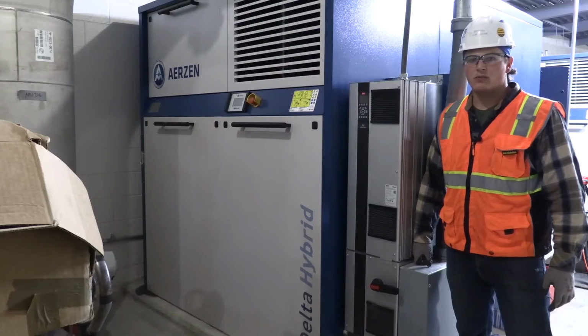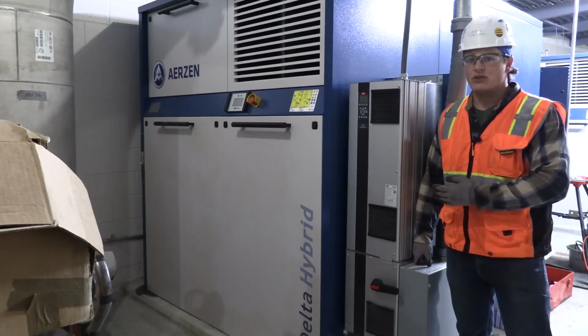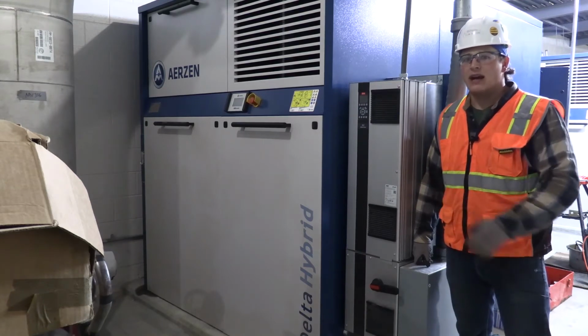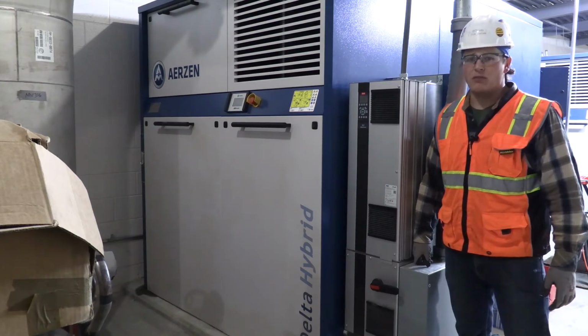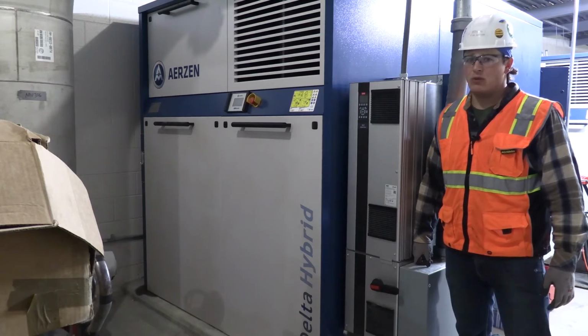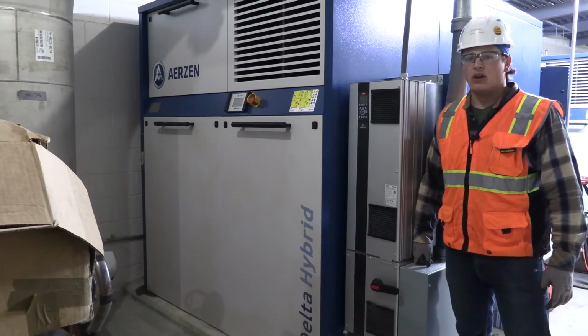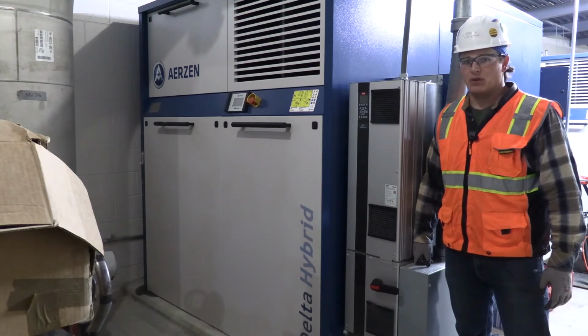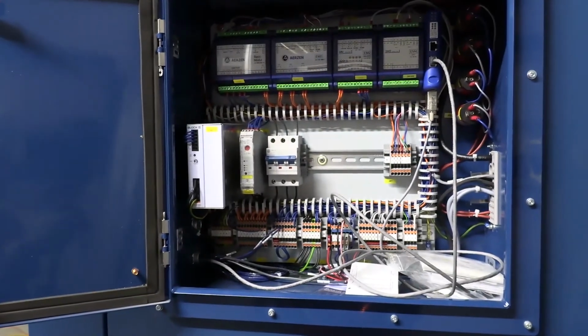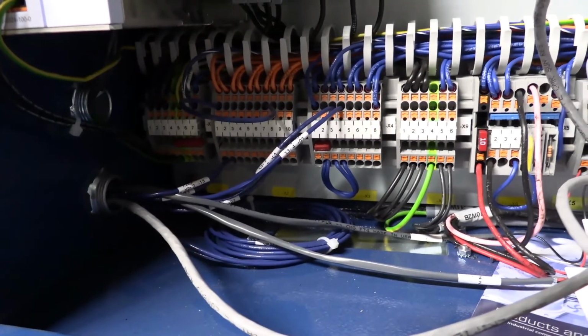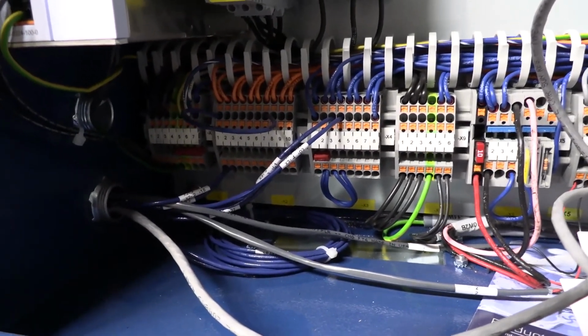When it comes to the blowers, we will need pictures of the VFD, motor starter, or controller for the blower. Not only will we need to see the control wires going back to our PLC, if they're individual wires or if it's a network cable, but we also need to see the main feed feeding the blowers to ensure that they are wired and ready to be powered up. If the blower has a PLC, additionally, if it has any other ancillary equipment like pressure sensors or temperature sensors coming into that PLC, we will need pictures of those also. Lastly, a picture of the motor showing the completion of the wiring.